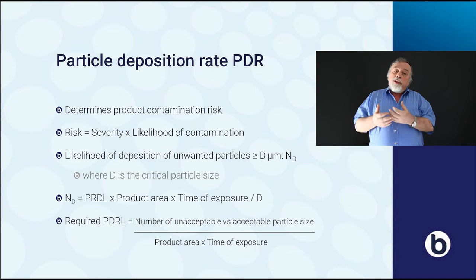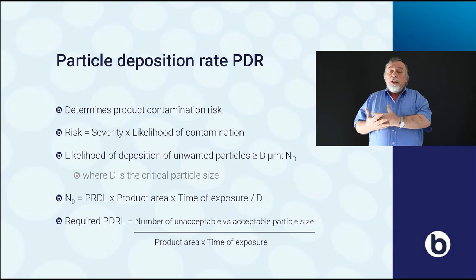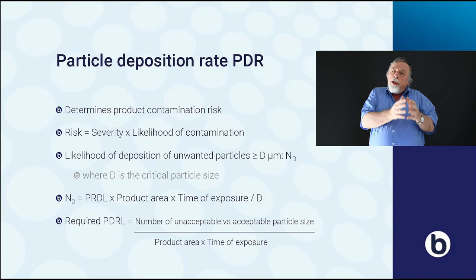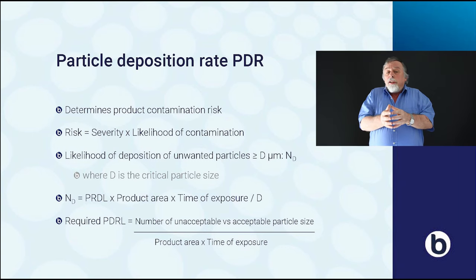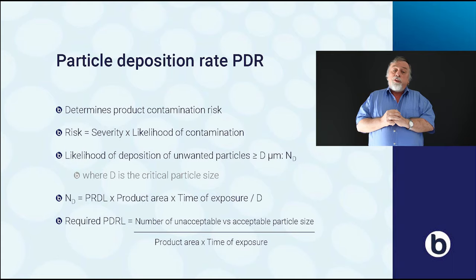You can also turn it the other way around and set requirements for the particle deposition rate level. In that case, the particle deposition rate level is derived from the number of acceptable particles for a certain particle size. You can accept a very low number of larger particles, or a slightly higher number of smaller particles. You divide this number by your product area and time of exposure to get your particle deposition rate limit.